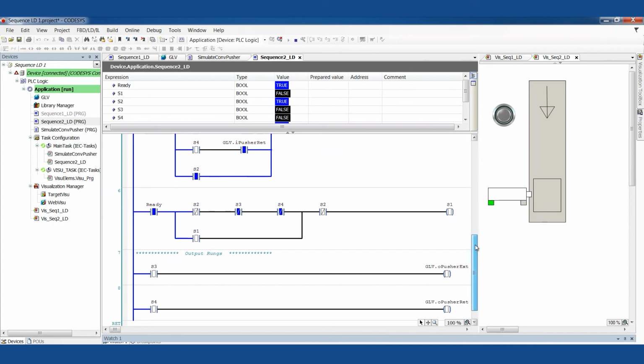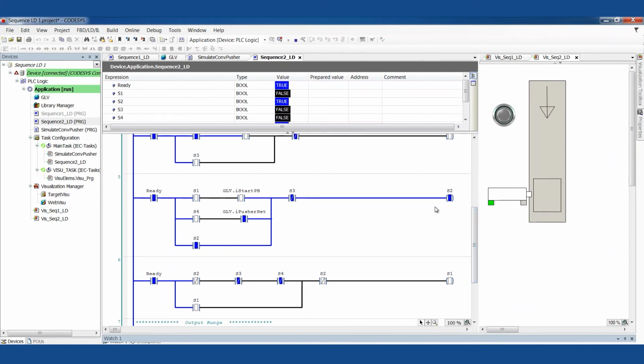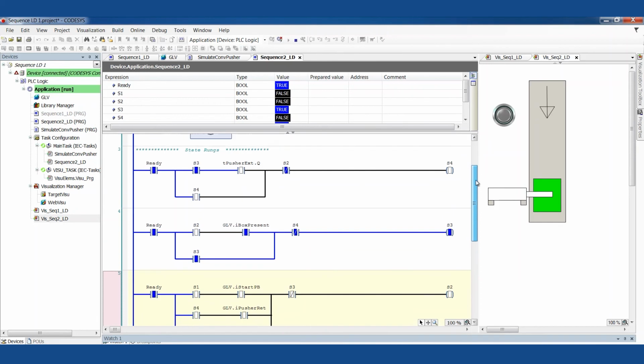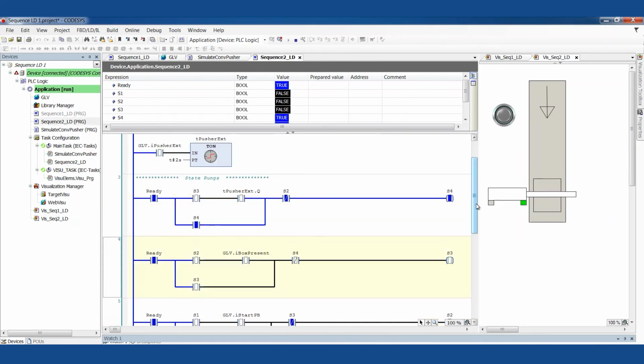it's not going to go back to state 1 because we're not waiting for the start button. We're waiting for a box to be present. That's what state 2 is. And in a real program, I might give these different names, something that actually makes sense. So I'm not suggesting just have state 1, state 2, state 3, because it's not very understandable by someone who doesn't have this diagram that we've made. Okay, so we've proven that this works. Box, step to the next thing, extending, step to the next thing, retracting, and step back to state 2. We've proven that this works.